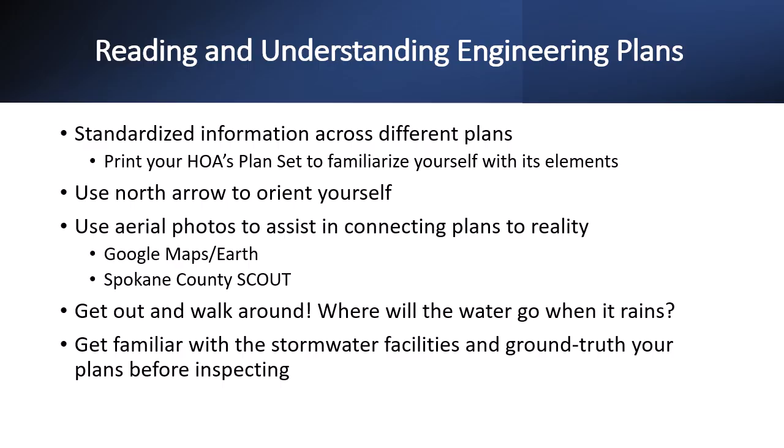as you find them. During this time, it might also be helpful to ground truth the plans in preparation for an inspection. This is important because the plan sets, even as built, may not always match what exists. In some cases, features that were planned were never built, and vice versa. You may want to note where there are differences.